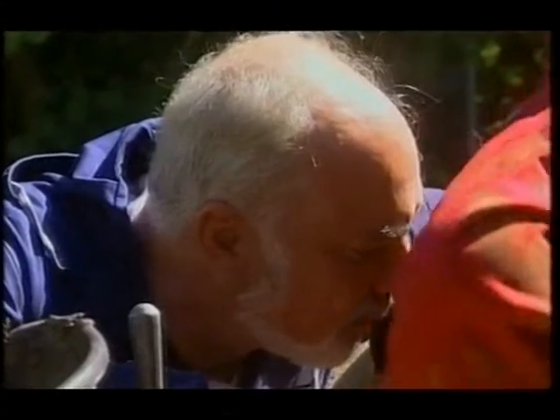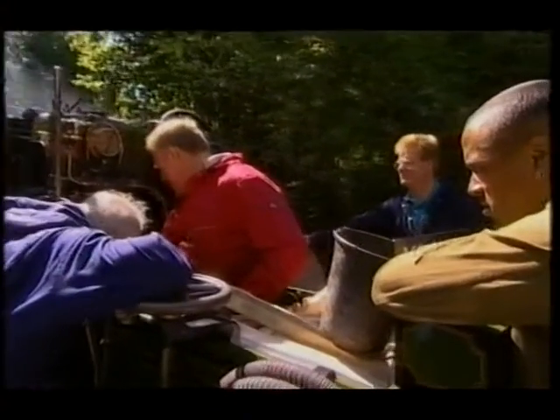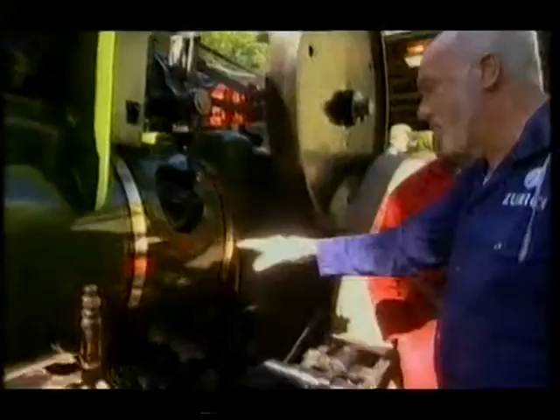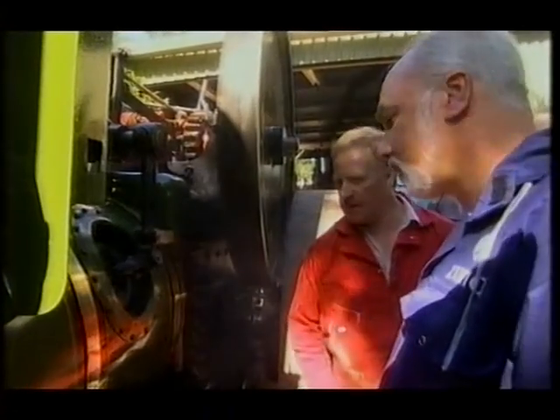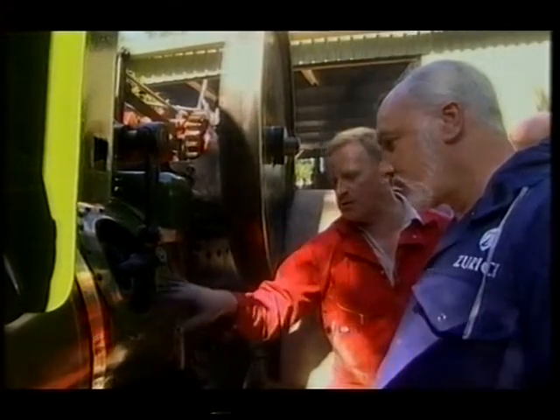That's right. Glenn has to be satisfied that every joint in the pipework and every rivet in the boiler is absolutely safe. Just one whiff of steam in the wrong place would mean no certificate and no trip to Dorset. It looks as though something's bubbling there. Yeah, that joint is new. New joint, is it? Yeah, and the compound oil seals it. Don't think it's steam because there's no sign of steam and no water coming through.